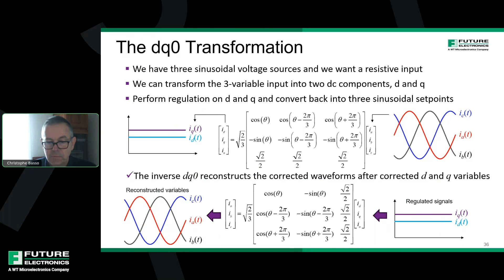And the way to go from a three AC variable frame to a two DC component system is to use the DQ0 transform, made of the Clarke and Park transformations. So you can see here, from the sinusoidal input, you go through this mathematical transform and you have two DC components. Then once the two DC components are regulated and changed depending on the power or the type of impedance you want to offer to the network, you go through the inverse transform to recreate a sinusoidal set point that will be sent to the modulator.